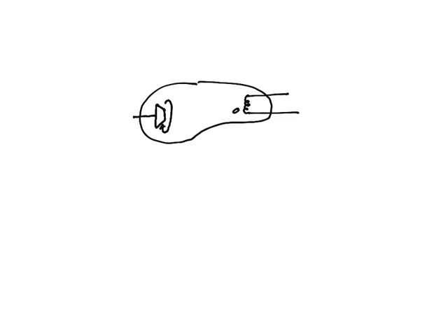So what that allows to happen is you have an electron, it still hits the wedge surface and gets directed downwards, let's say towards the film, but now it's also spinning, so that as time progresses, you're hitting different parts of this wedge-shaped anode. You're not always hitting the same spot. If it spins, you're always hitting the wedge, an angled piece, but it's a different part of the wedge. And so this was the final evolution, basically, to what we have today, into how to create X-rays to make an image.